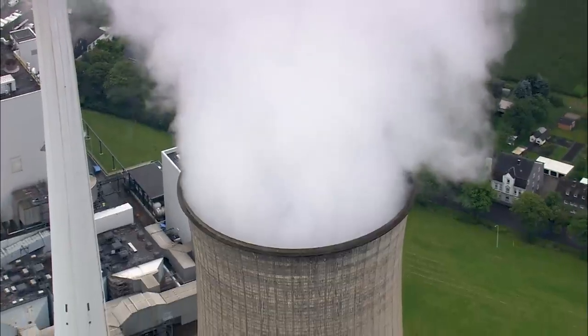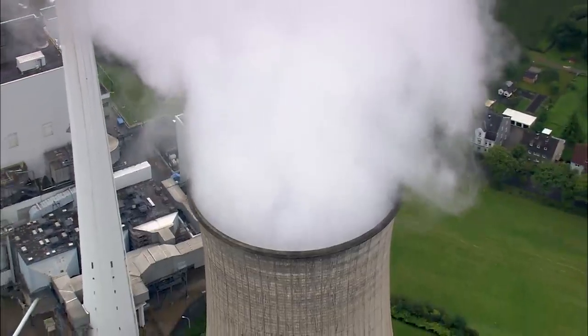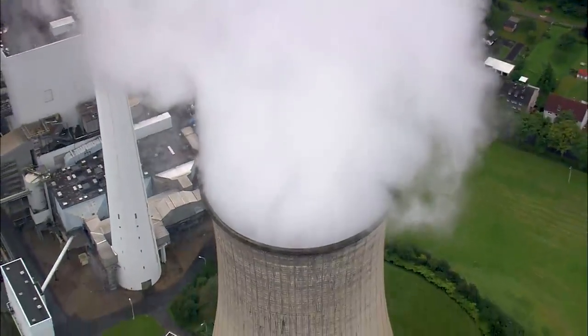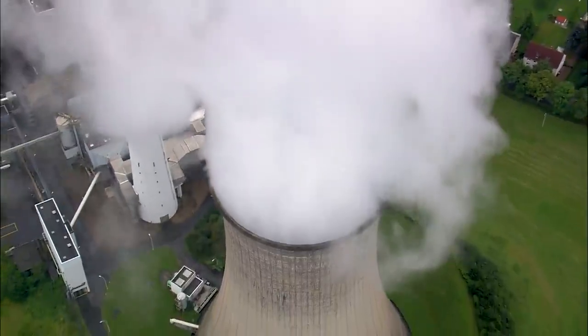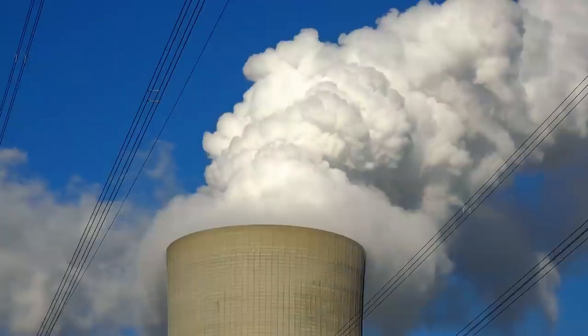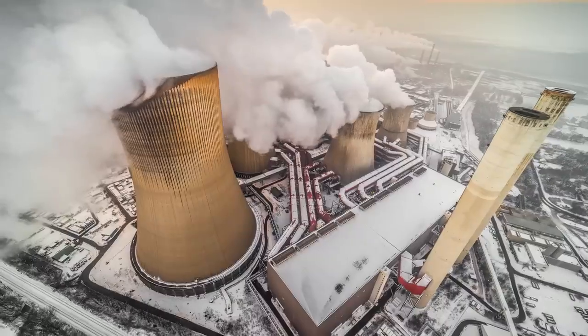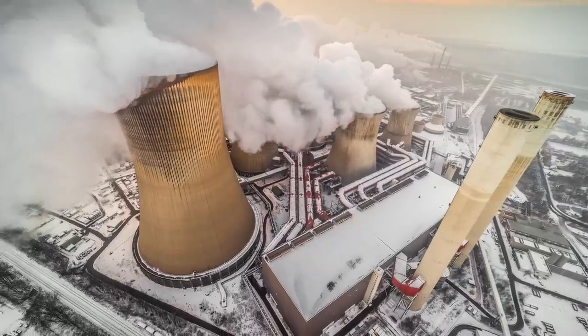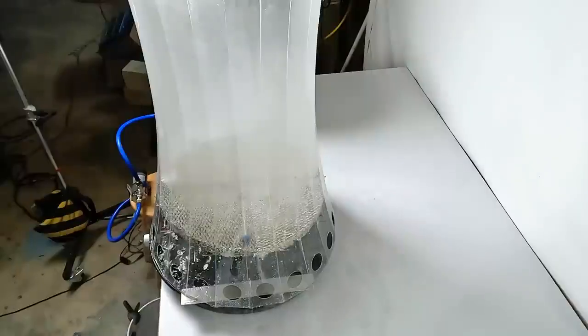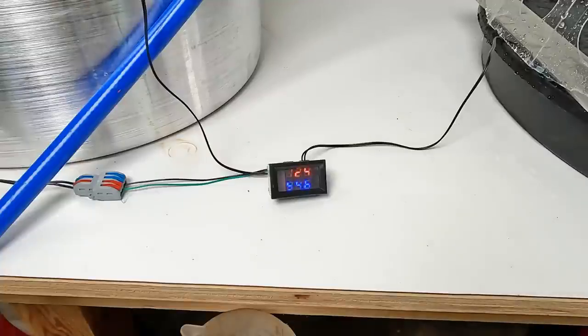It's not actual smoke, it's just water vapor condensing into tiny droplets as the now saturated air mixes with the cooler outside air at the top of the stack. It's basically a cloud machine. That's why the plume is usually more visible during the winter months. I was really surprised at how well my little model tower worked. I was pumping water at about 120 Fahrenheit or 50 Celsius, and the water coming out was dropping by around 30 degrees F, 17 degrees C.